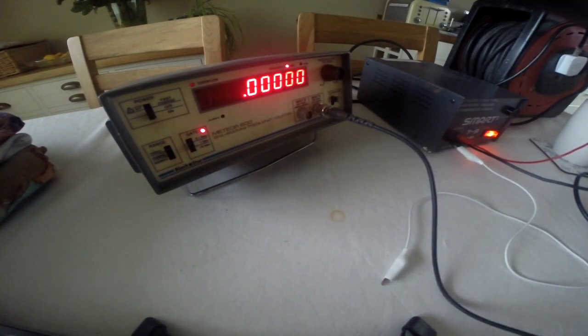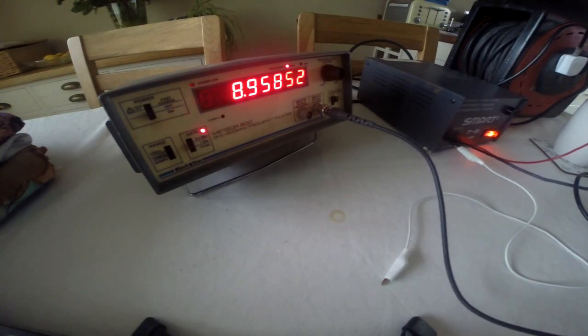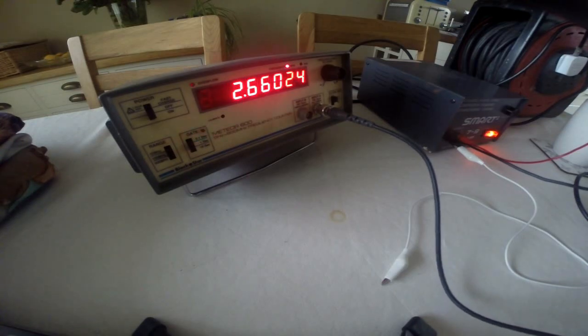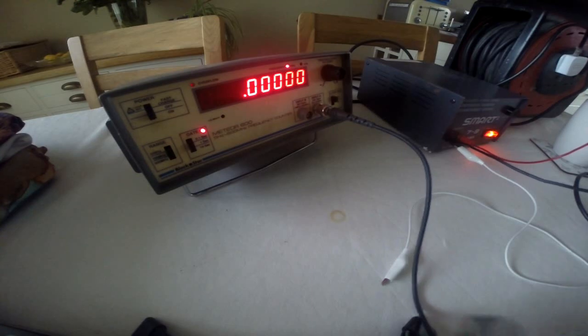So, on upper sideband, again, if I can get the probe on there, and get it to stay on there. Right. So we've got 10.69488, should be 10.695. Go to lower sideband, should be 10.692, which it is. Then back to upper sideband. So we're within spec on those two measurements.